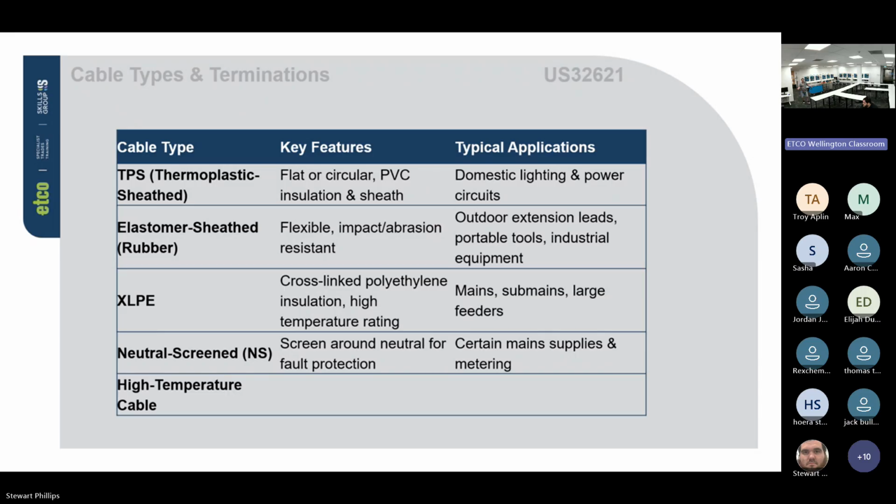For the people that don't listen, like I was talking about, Dave, come on. Volt drop. Are you on volt drop? We mostly talked about the simplified method. So just so you guys know, the volt drop standard is AS/NZS 3008.1, and that has most of it in there. Other than that, it's in section C of AS/NZS 3000. Yeah, they found the table in section C.